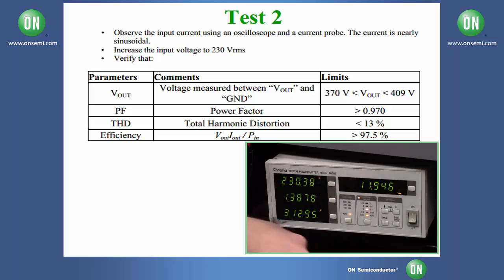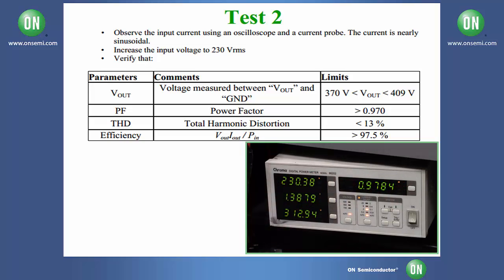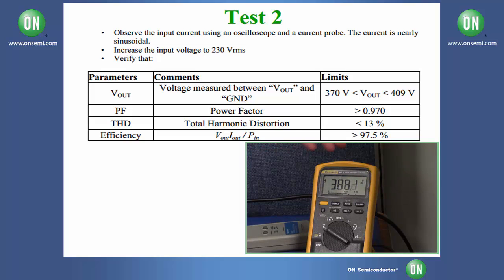And then we're going to also check once again that our THD is below 13%. And once again we're going to measure our efficiency. And in this case it turns out to be approximately 97.5%, which is acceptable. And we also verify once again that our PFC output voltage is between 370 and 409 volts DC. And this concludes test 2.